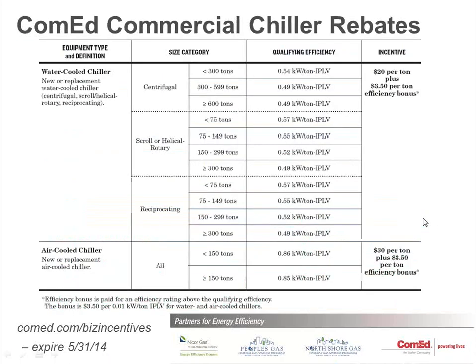Looking at a couple of them in detail, this is the chiller one, and this is how it basically works. You got to decide if it's a water-cooled chiller or an air-cooled chiller. For example, if it's an air-cooled chiller, then you got to say, is it above or below 150 tons? Then they give you a target to hit, 0.86 kW per ton, for example, for a smaller chiller. They give you $30 per ton, assuming you can hit that target, plus every 0.01 kW per ton better than the 0.86 that you do, you get $3.50 extra. So if I put in a 0.84 kW per ton IPLV chiller, that's 0.02 better, so that's $7 bonus. So I would get a $37 rebate, right? That's kind of how that would work.